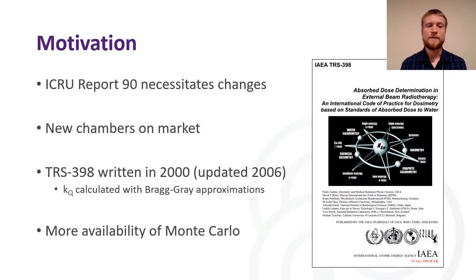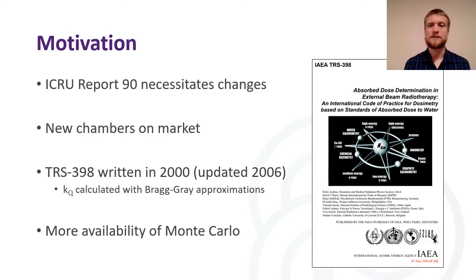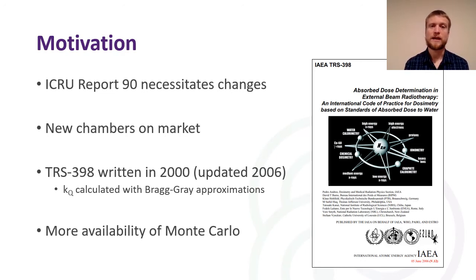This work is also motivated by the publication of ICRU report 90, which necessitates changes so that there is consistency across the entire dosimetry chain, even though we expect the differences to be small. There have been many new chambers placed on the market since the publication of TRS-398, so allowing KQs to be put in a protocol for those is important. TRS-398 was written in 2000 and updated in 2006, and the KQs were calculated with Bragg-Gray approximations and cavity theories. With more availability of Monte Carlo programs, research groups, and high quality data, the ability to do this more accurately continues to improve.